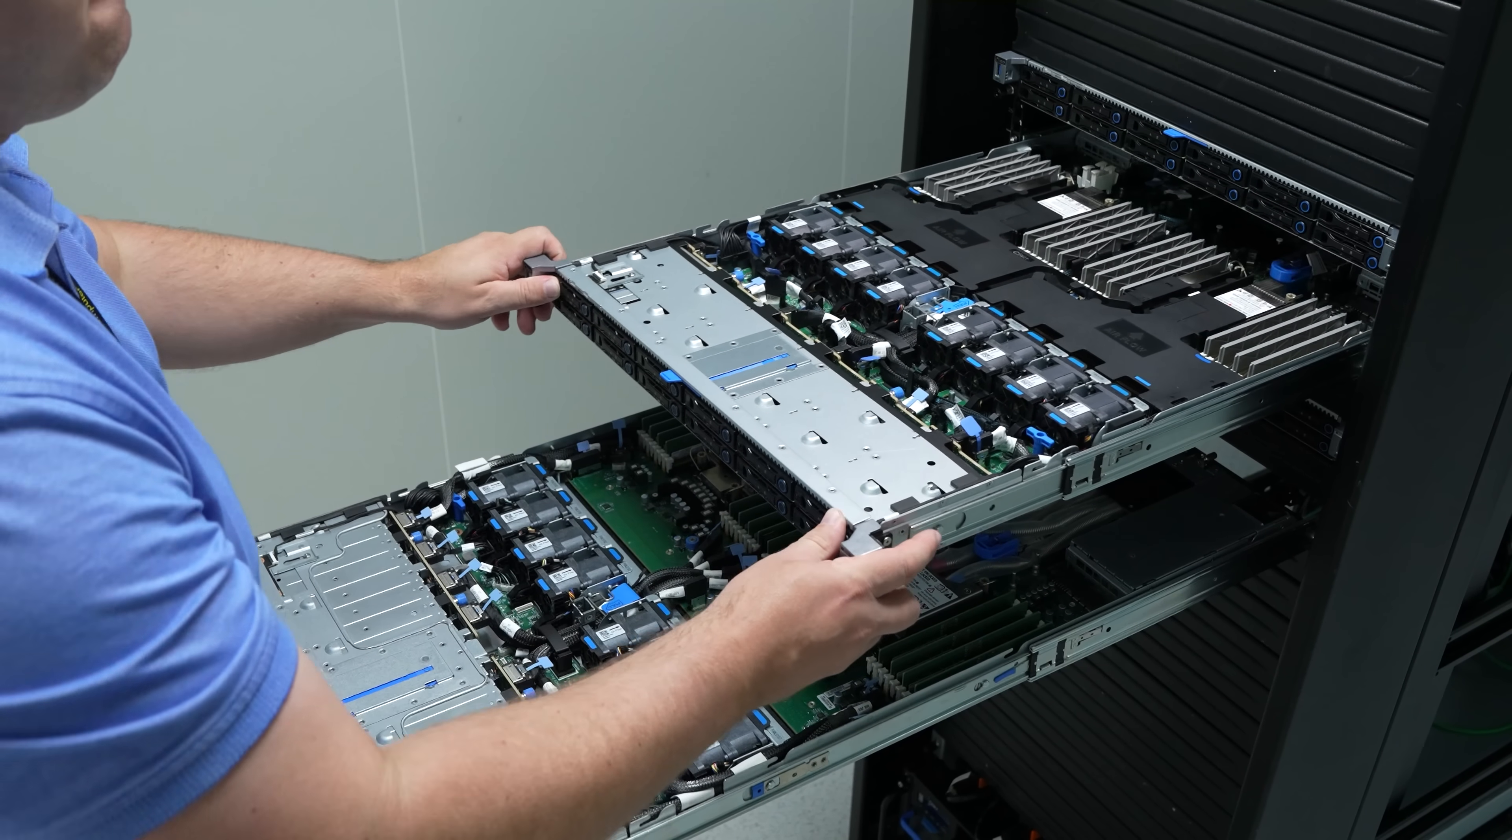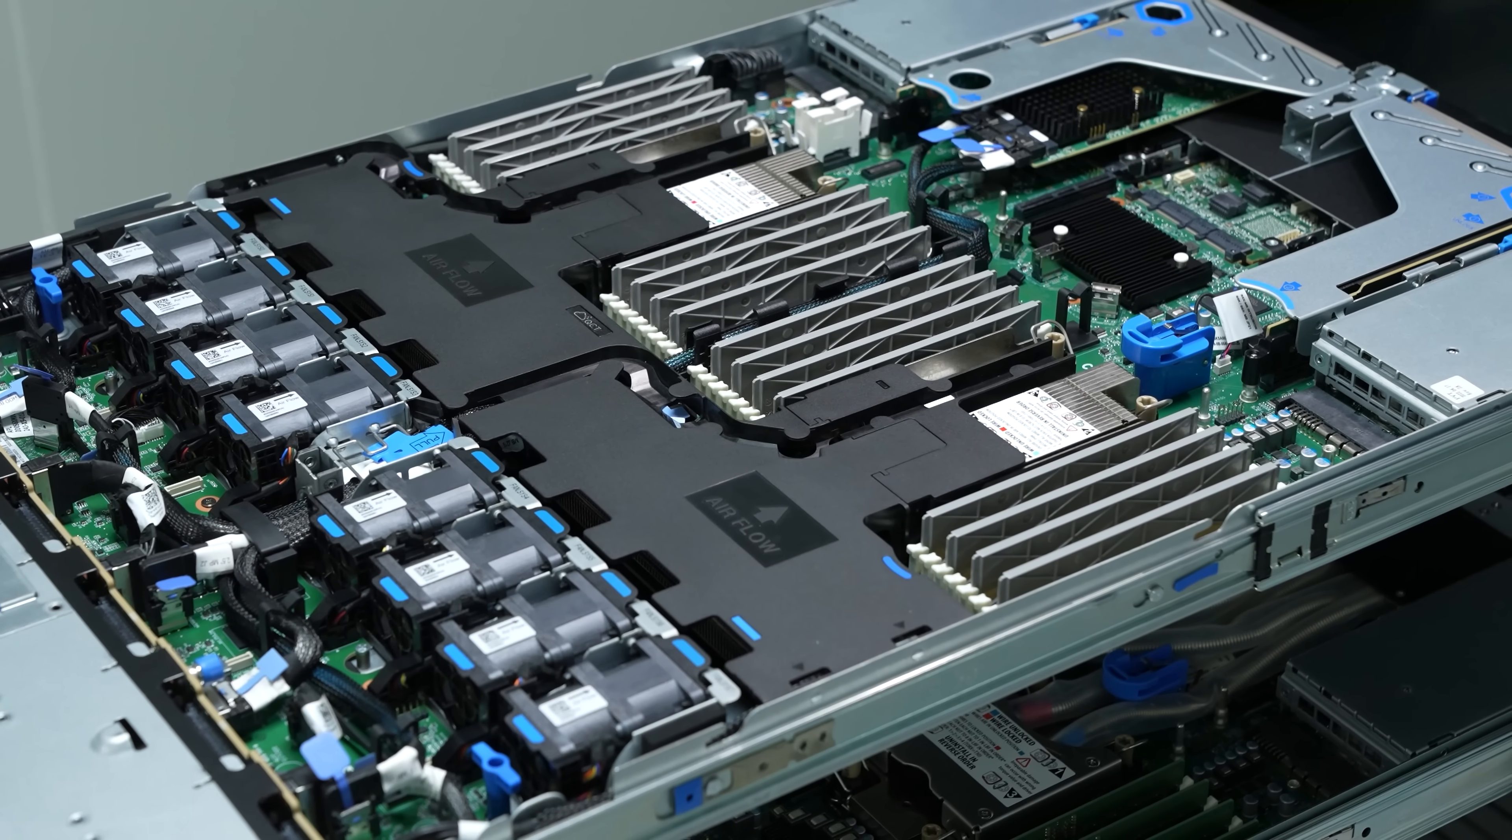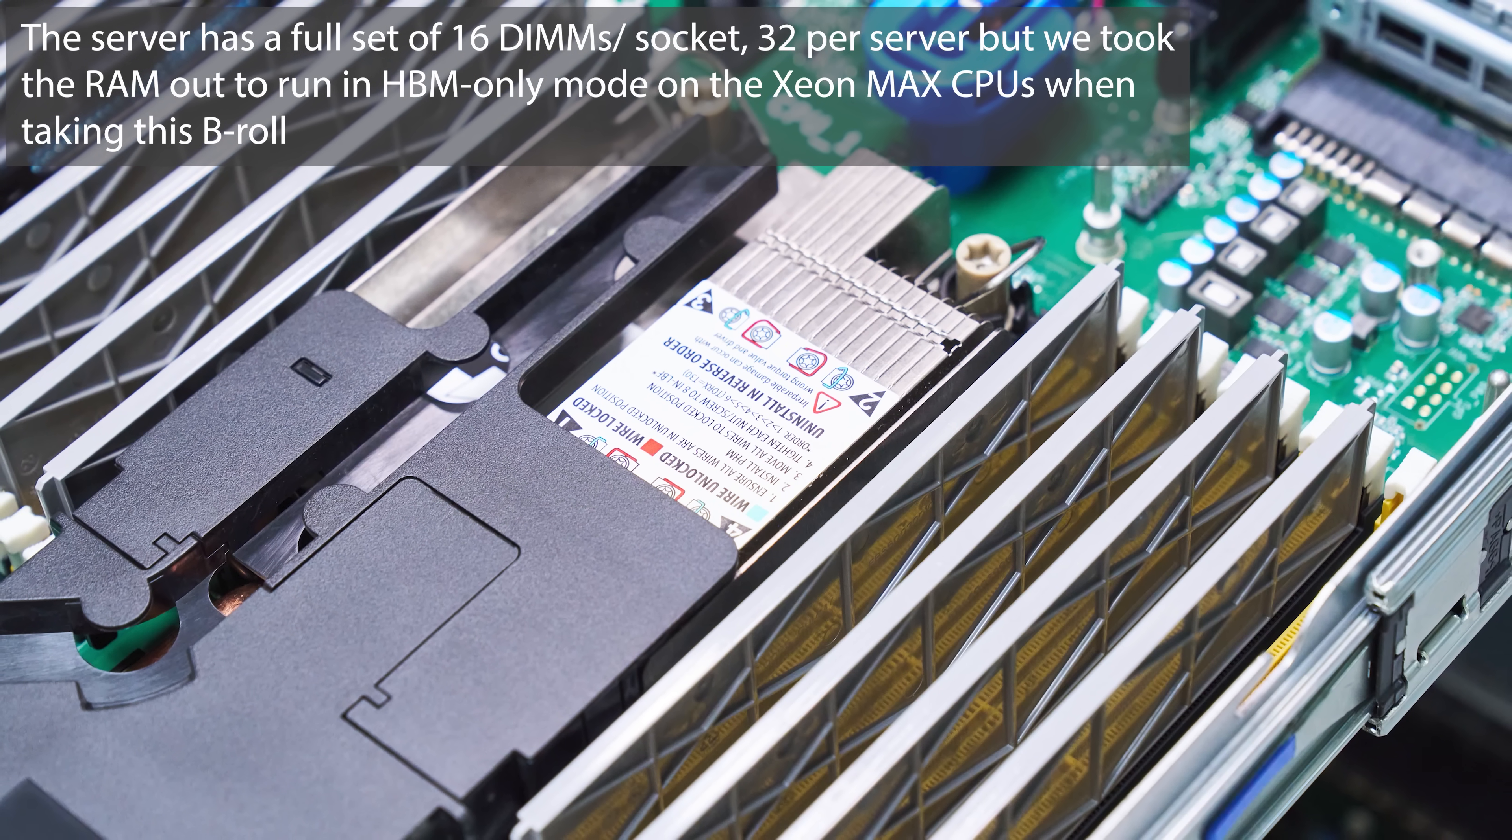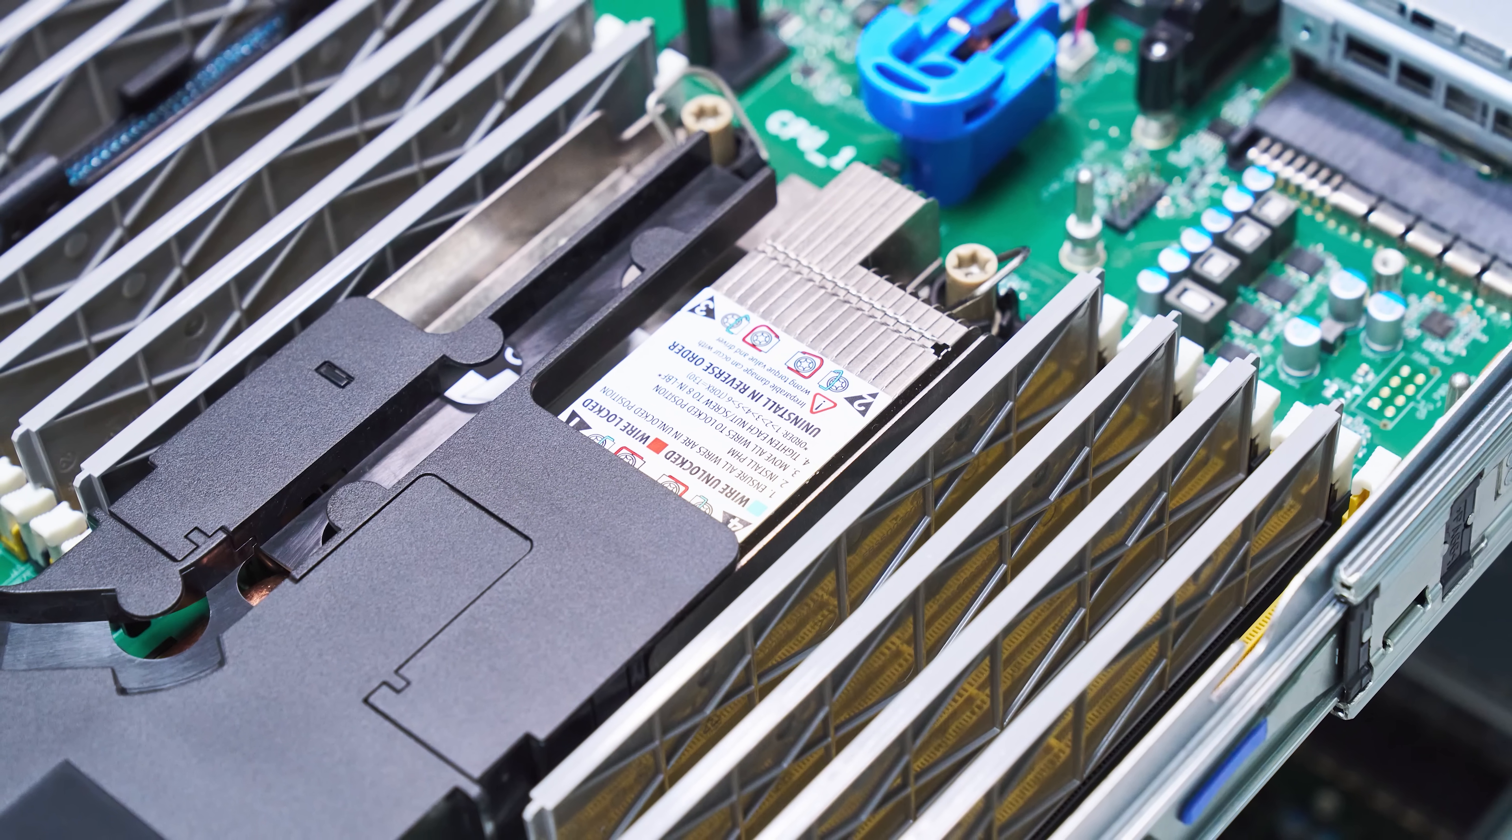You can see that the liquid cooling goes from the rear of the server in the cool loop. It goes through the two CPU blocks and then out of the back of the server. And even with that, you still have your RAM. You have your ability to add in cards and your different SSD options. I think you'll remember that we had both two and a half inch as well as E1S options on the front of these servers. I will just point out, though, that liquid cooling does take up one of the expansion slots. And then just to be complete, we're going to show you the air-cooled version of this. You're going to see that we have much larger heat sinks. And these days, server processors are so hot than like 1U form factor, especially if you're going to have a full set of DIMMs like this server does. You need to have little ears or dog ears or, you know, whatever you want to wing. Some people call them like whatever they are. You need to have some extra extension on your CPU heatsink. Otherwise, you just simply can't cool the modern CPUs in a standard just kind of like 1U socket size.